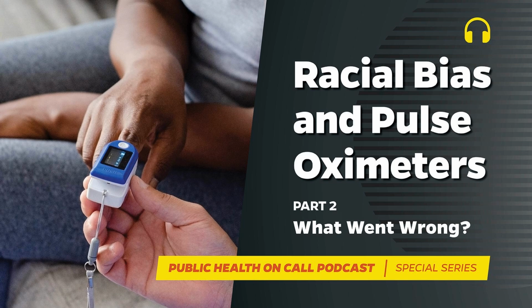For pulse oximeters and other medical devices, the FDA also sets testing standards. The agency recommended that manufacturers include at least 2, quote, darkly pigmented subjects, or 15% of the study participants, whichever is larger, in their pre-market studies. But this recommendation is not a requirement. And as we've learned, skin pigmentation classification has historically been exclusively subjective and often inaccurate. This is the standard still in use today.